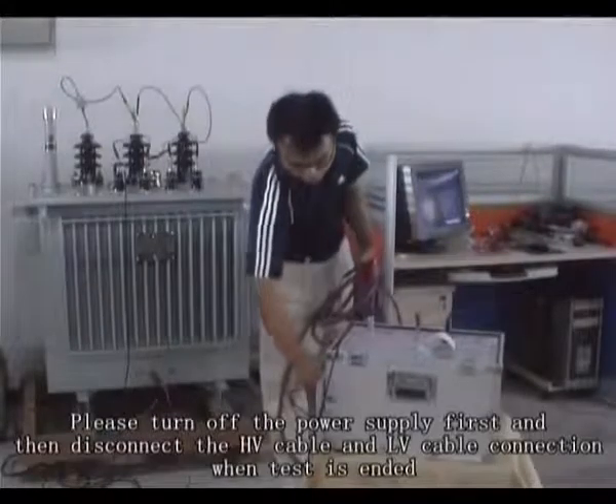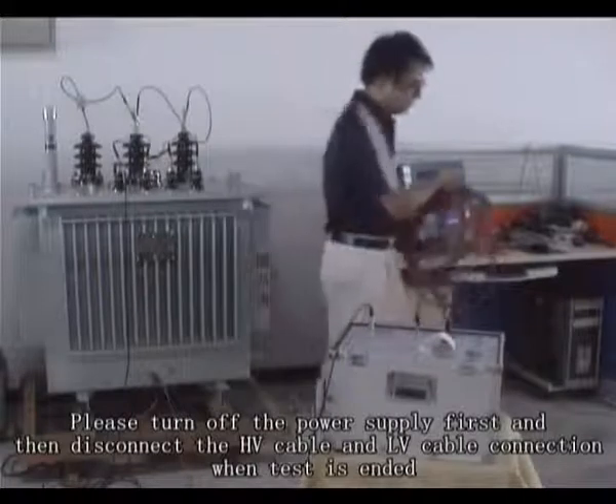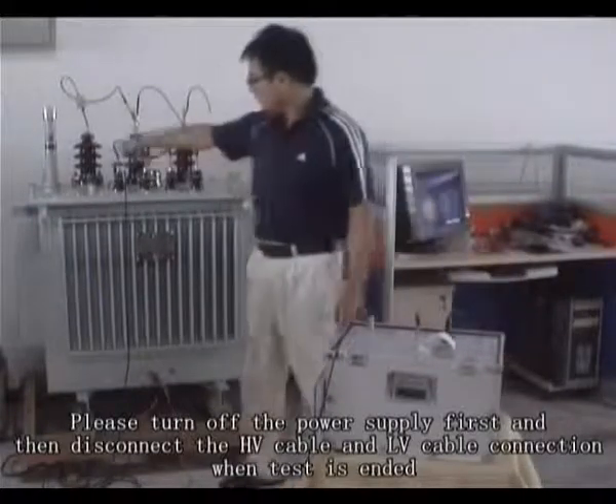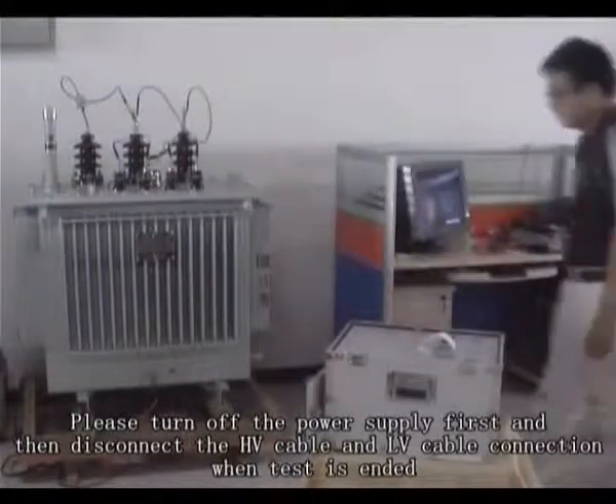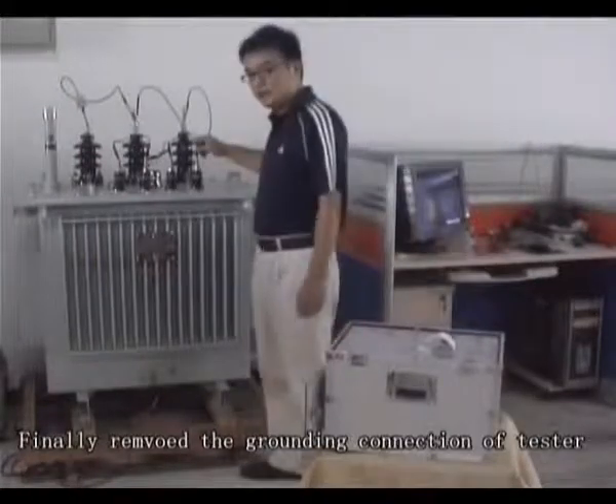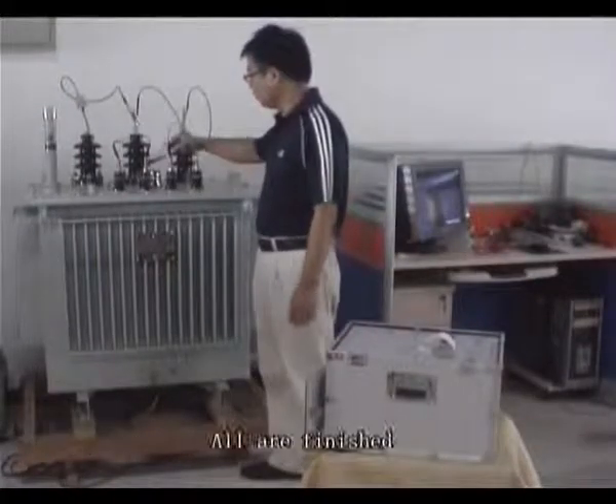Please turn off the power supply first, and then disconnect the HV cable and LV cable connection when the test is ended. Finally, remove the grounding connection of the tester. All are finished.